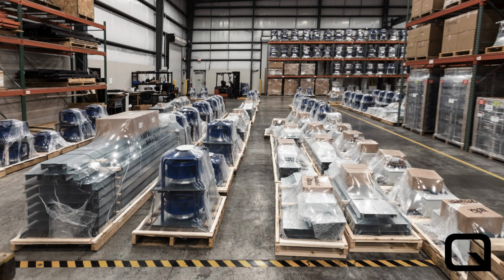So Q-PAC's fan frame has a lot of benefits for a contractor or an installer. The main benefit is that it's covering extra scope that a traditional fan replacement wouldn't usually cover. If a fan fails and you get an exact replacement, it's not going to come with a bulkhead wall, a pressure wall, or a fan frame that covers the entire cross section of the air handler. The Q-PAC MPF covers the scope that other fans won't. So it's not only the electrical or the control scope, it's also the full structural scope, and it makes it super simple to integrate into the air handler.